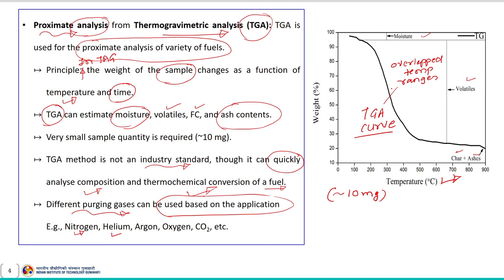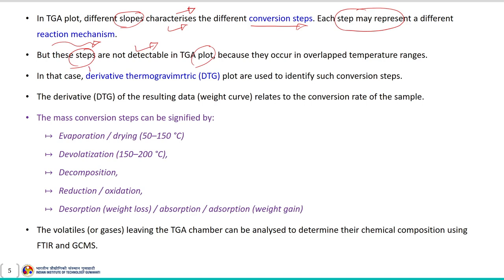For example, taking the case of biomass, the hemicellulose contained in the biomass may overlap with the decomposition pattern of cellulose, because of the overlapping temperature ranges of decomposition of these different compounds. Hence, it is very difficult to detect this step in a TGA curve. In that case, the first derivative, also known as the derivative thermo-gravimetric plot or DTGA plot, is used to identify such conversion steps.